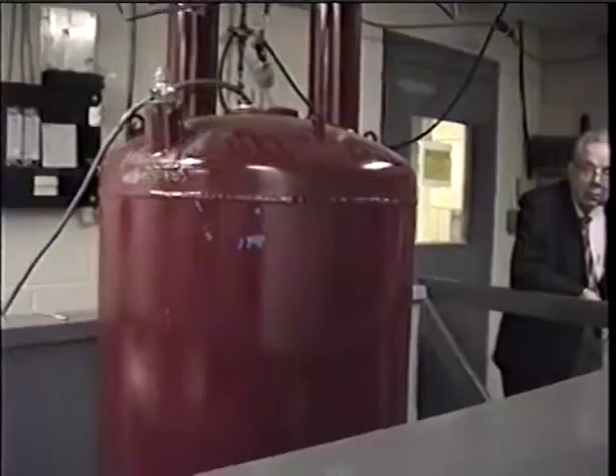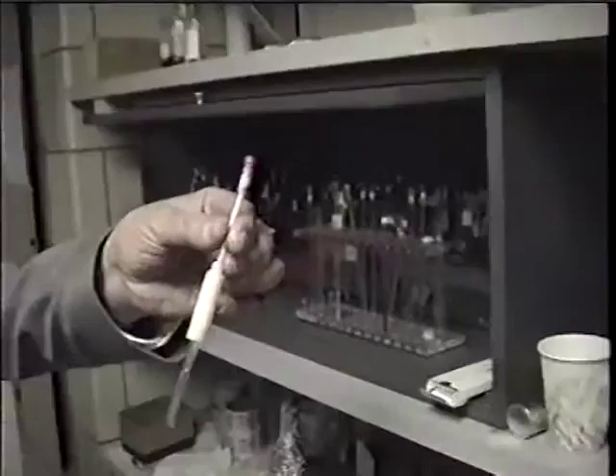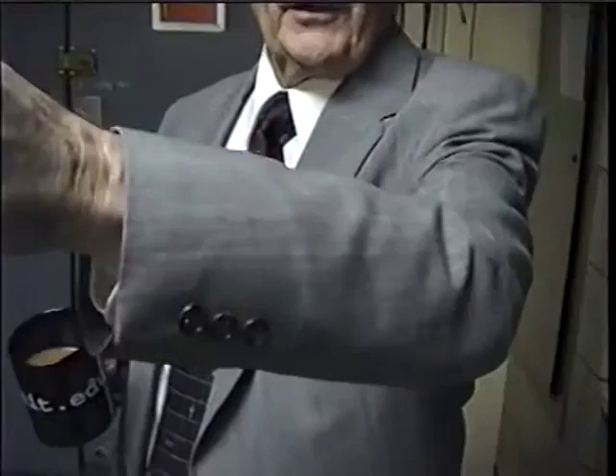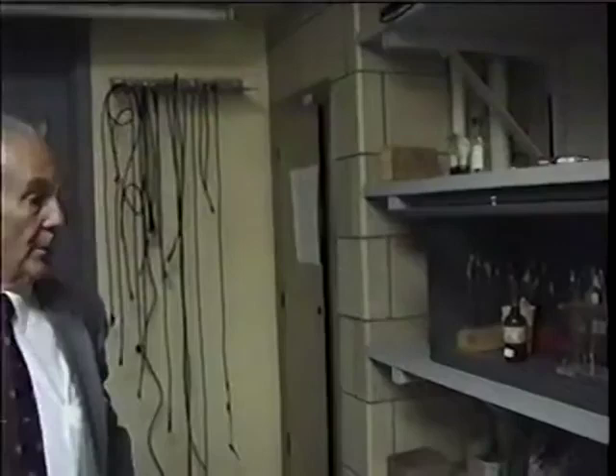And the probe, which holds the RF circuitry, goes into the magnet. It's on that stand you can see there. And the sample is first put into a small spinner, air spinner. That's what does the rotation then in the magnetic field. And it's dropped into the center of the magnet, in the center of the coil. And that's how the interaction between RF energy and the nuclei of the particular atom you are looking at works. And that's what we call 5 millimeter sample tube, which is the most popular. There are, of course, other dimensions for different uses.